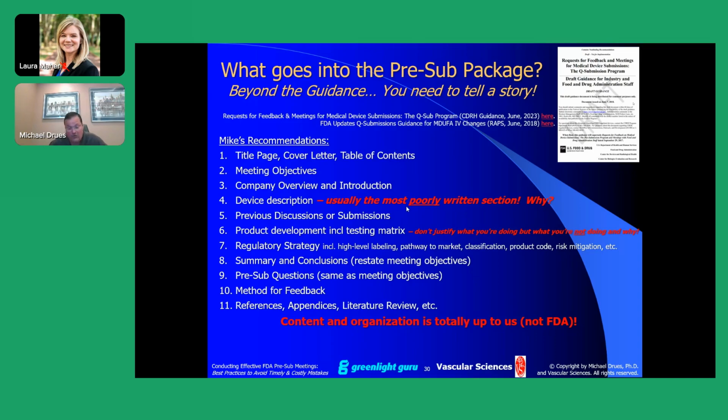One of the big advantages of the pre-sub, unlike a final submission, is that it is 100% up to the company what to talk about. You tell the FDA what you want to talk about. You tell the FDA what you don't want to talk about. The content and the organization is totally up to you.